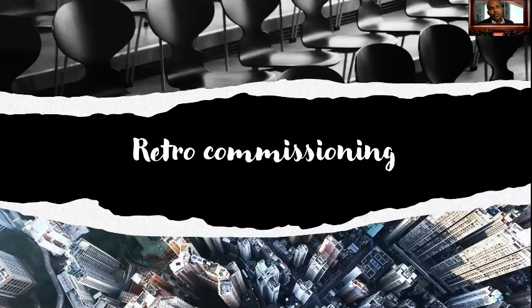So that brings us to retrocommissioning. Retrocommissioning is a process to improve the efficiency of an existing building's equipment and systems. And why am I bringing this up as a strategy? If you have older buildings, with all those air conditioning systems, half of them may not be working, half of them may be working, but this is the time to think about recalibrating, having an audit, or at least having a person do a retrocommissioning where you can have a step-by-step process on, if you want to replace the system with a newer system, what is the payback, what is the life cycle analysis, and things like that.